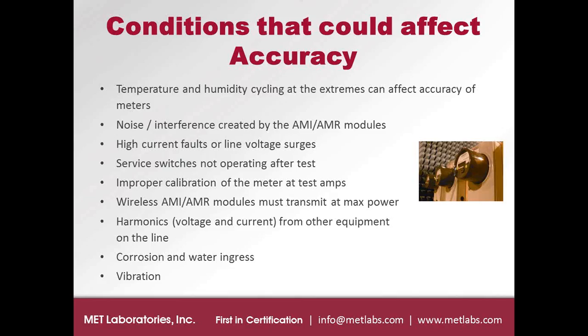So we run an as-received test sequence, full load, light load, power factor when we first get the products, just to make sure that the meters are properly calibrated at test amps and also at the light load and 0.5 lagging power factor as well. You want to make sure, again, that the communication modules internal to the meter are transmitting at full power. Harmonics certainly could affect the accuracy of the meter, although for the ANSI program at this time, there are no harmonics tests that are listed as criteria, but that could change in the future, and I think very will likely change.